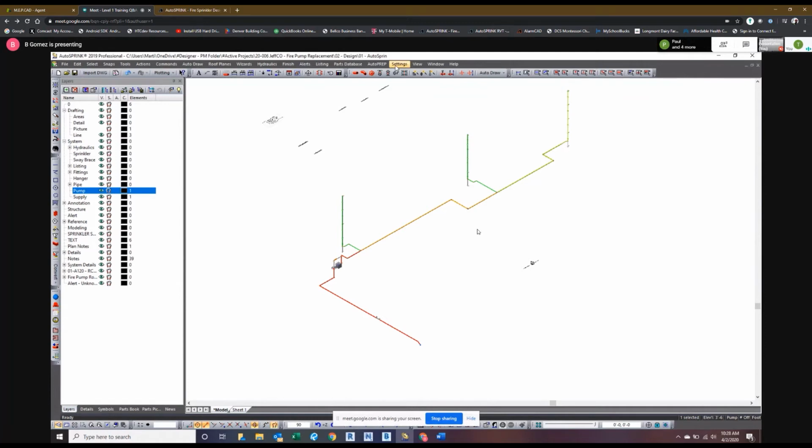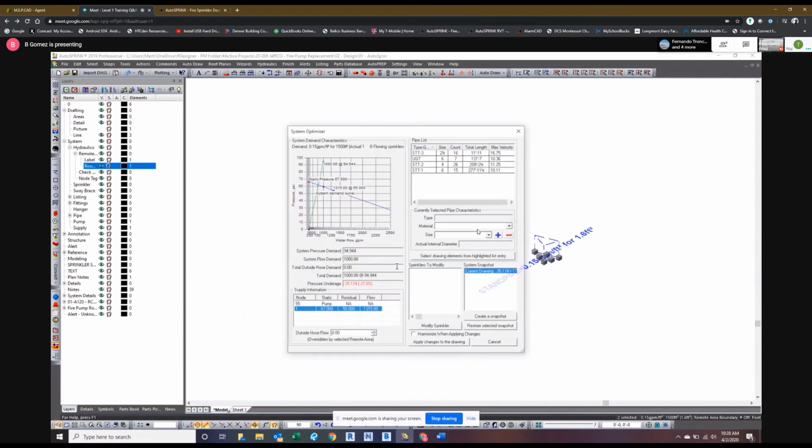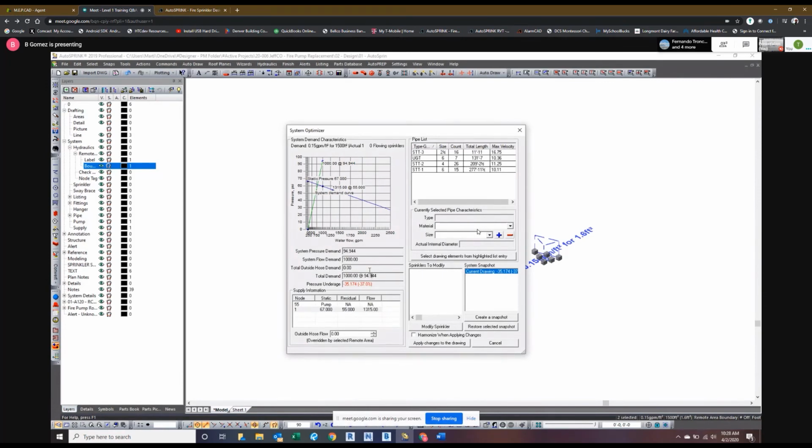If you change the default properties of the three remote areas, standard, boundary, and box. The way I had set up these settings is by default, I had specified a hose allowance override for each of those three remote areas. And for some reason, the program is pulling that hose allowance data from the remote area default properties and applying it in the hydraulic calculations. Yeah, it's funny because when I drop a remote area, just any one, and I calculate it through that, it takes it away. Yes, sir.